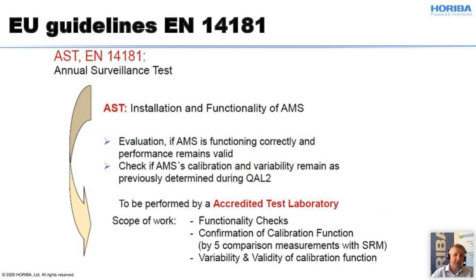And finally, we also have the definition of the AST, the so-called annual surveillance test. The annual surveillance test is necessary so that after a certain period of 1 year, the instrument needs to be checked and the functional tests need to be performed. We need to confirm the calibration function by a comparison measurement with a standard reference method instrument.